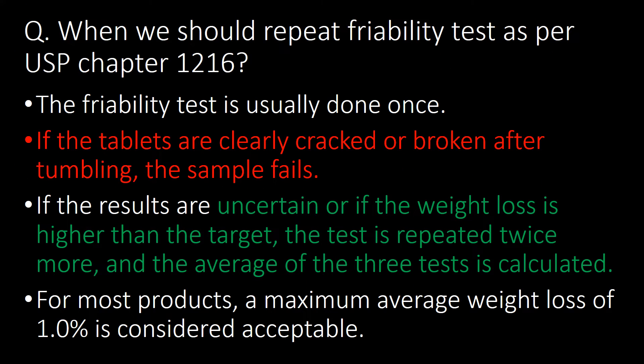When should we repeat the friability test as per USP chapter 1216? The friability test is usually done once. If tablets are clearly cracked or broken after tumbling, the sample fails. If results are uncertain or weight loss is higher than the target, the test is repeated twice more and the average of the 3 tests is calculated. For most products, a maximum average weight loss of 1% is considered acceptable.